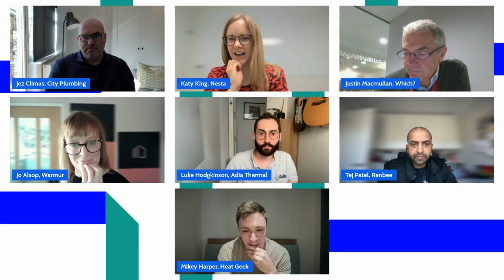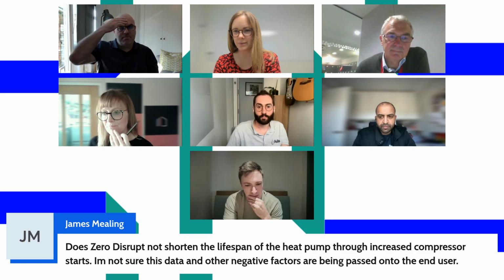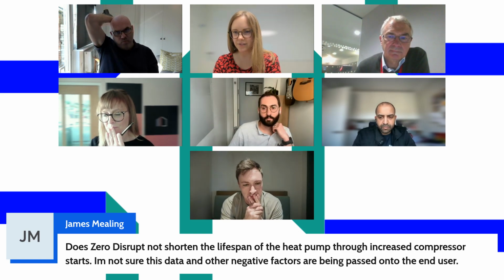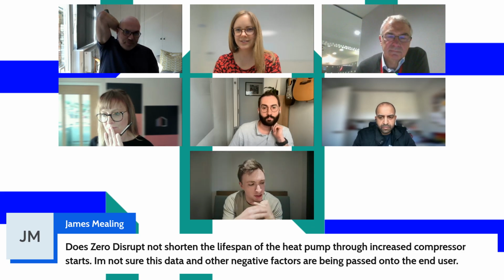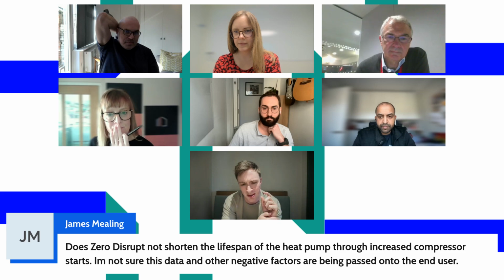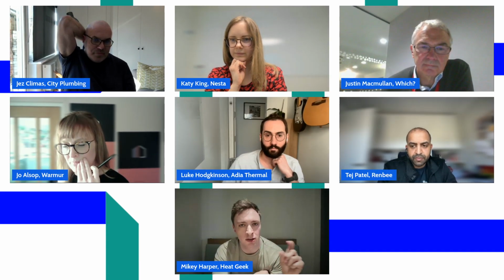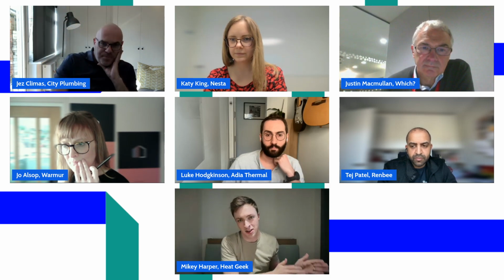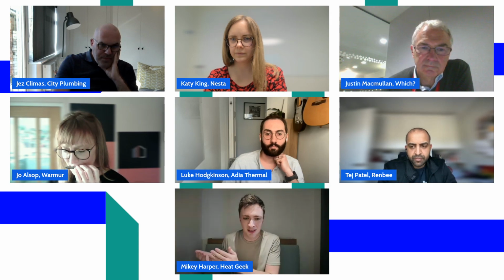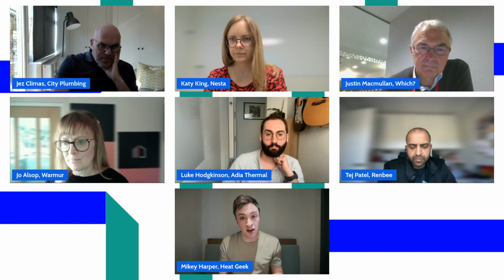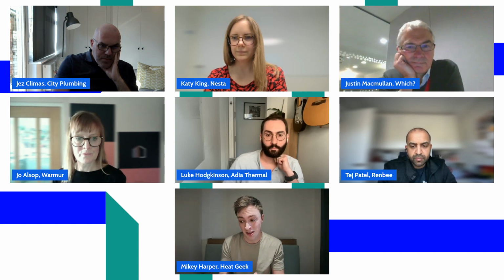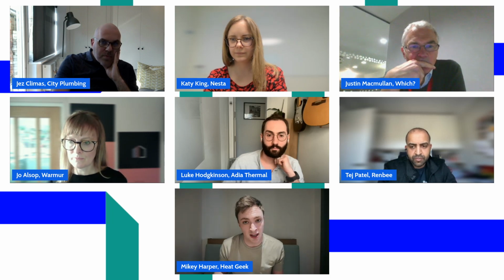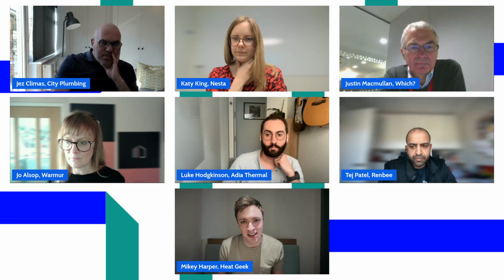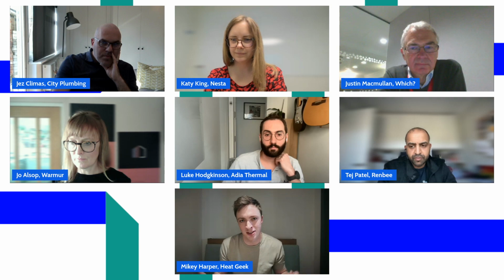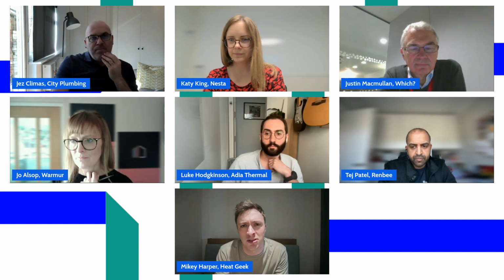Does zero disrupt not shorten the lifespan of the heat pump through increased compressor starts? I'm not sure this data and other negative factors are being passed on to the end user. We're very cautious on the heat pump's limits and work closely with manufacturers on these. To clarify, a zero disrupt install shouldn't result in a change to compressor starts - increased compressor starts tend to come down to poor design. These are still designed with short cycling in mind, so we're avoiding short cycling. They may run harder, but within the R290 heat pumps available on the market today, well within their operational bounds, and we maintain the warranty with manufacturers. So it'll be interesting to see. I'd love more data. We're doing everything we can today to make sure the designs have no detriment to the long-term performance of these systems.